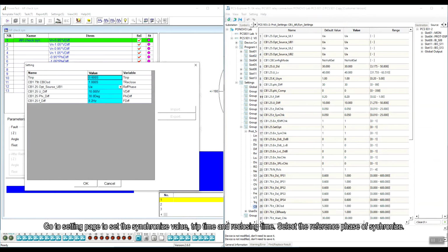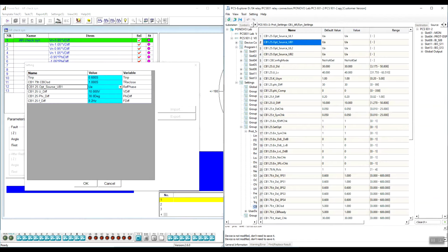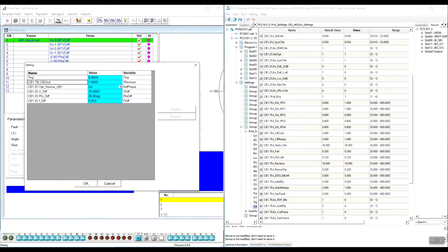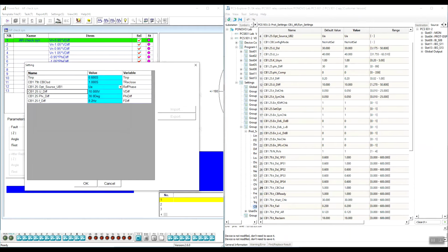Go to setting page to set the synchronized value, trip time, and the reclosing time. Select the reference phase of synchronize. Reference phase of synchronize is UA. The reclosing time is 1 second. The voltage difference is 10 volts. The angle phase difference is 30 degrees. The frequency difference is 0.2 Hz.